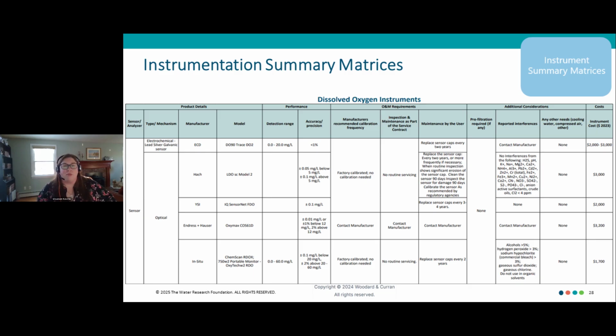This summary has the instruments broken down by whether they're sensors or analyzers, then shows the method for the measurements, and the analytes in that final column. We actually have two summary matrices in the app: broken down by sensor or analyzer as shown here, or broken down by the analyte itself. So if you're trying to do ammonium, you can do either a sensor or an analyzer. DO, you're just going to have sensors available. So it's broken down two different ways in the summary matrices.